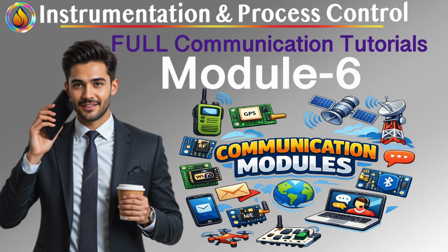PA is designed specifically for process instruments, bus-powered devices, intrinsically safe environments, pressure transmitters, flow meters, control valves. These devices don't need millisecond updates. They need reliability, diagnostics, safe power delivery, stable communication. PA trades speed for process suitability. It allows power and communication on the same pair, safer operation in hazardous zones, rich device diagnostics. PA answers a very different question: "Is this measurement trustworthy, healthy, and safe?"